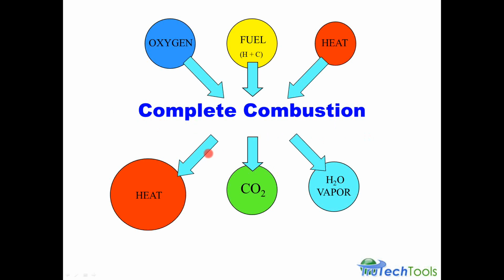When complete combustion happens, we get more heat released from the bonds in the fuel. We get carbon dioxide produced, CO2, which is very different from CO. So let's make sure we understand this: CO2, carbon dioxide, is very different from CO. We'll cover CO in a little bit. And we get water, H2O. You can easily see the O's coming through in CO2 and into the H2O, the H's from the fuel coming through in the water vapor, and the C's, the carbon in the fuel, coming through in the carbon dioxide. So everything is chemically balanced here. We've also released a larger amount of heat than the heat we put in, the heat that's been transformed and comes out. A combustion analyzer looks at everything on the bottom side of the equation.